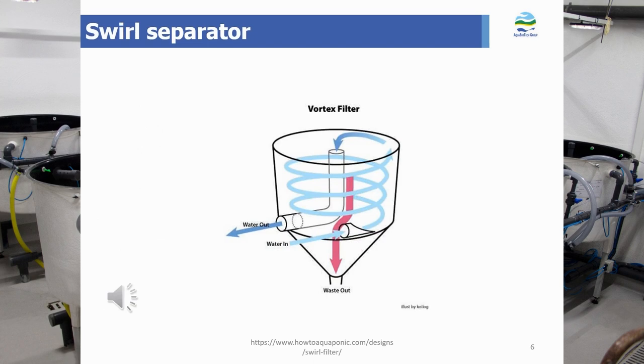Another common method to remove solid particles is the swirl separator, also called a radial flow vessel. It is a conical-shaped vessel where water enters tangentially from the bottom or top, creating a downward vortex that directs suspended materials to the bottom where sludge deposits and can be removed by siphoning or a valve. Clean water leaves the vessel from the top via an overflow pipe and returns to the system.